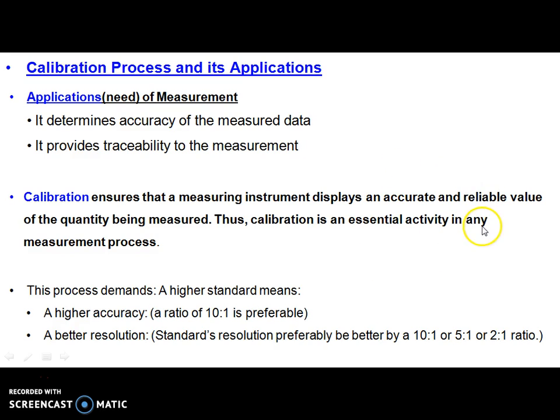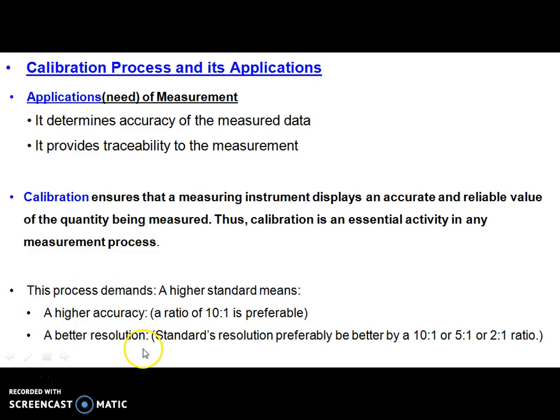There is one important relationship we should understand when going from the measurement process to the calibration process. The requirement of accuracy — the standard accuracy relative to the accuracy of the instrument under evaluation — is 10 to 1. So the standard used for calibration must be 10 times more accurate than the instrument under consideration, and it should have higher resolution as stated by this ratio.